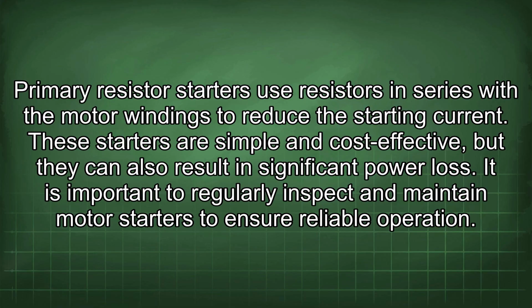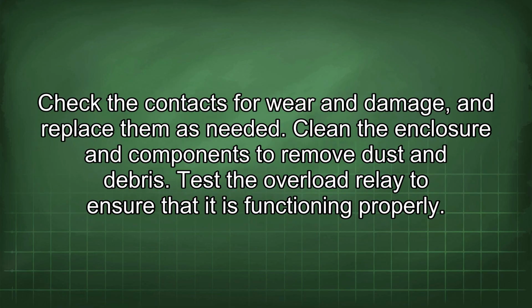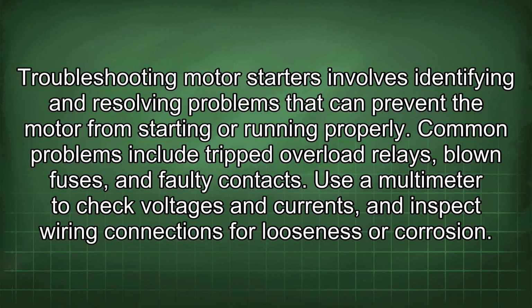It is important to regularly inspect and maintain motor starters to ensure reliable operation. Check the contacts for wear and damage, and replace them as needed. Clean the enclosure and components to remove dust and debris. Test the overload relay to ensure that it is functioning properly. Troubleshooting motor starters involves identifying and resolving problems that can prevent the motor from starting or running properly. Common problems include tripped overload relays, blown fuses, and faulty contacts. Use a multimeter to check voltages and currents, and inspect wiring connections for looseness or corrosion.